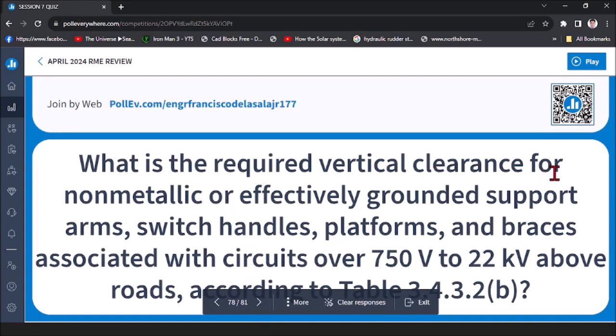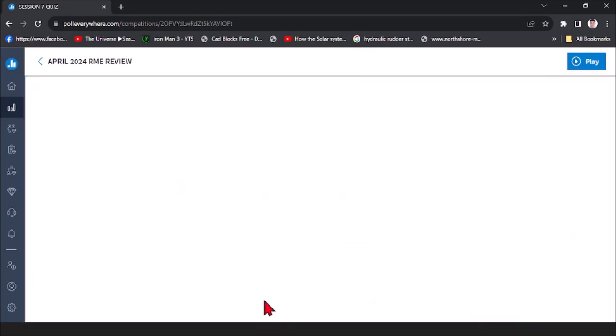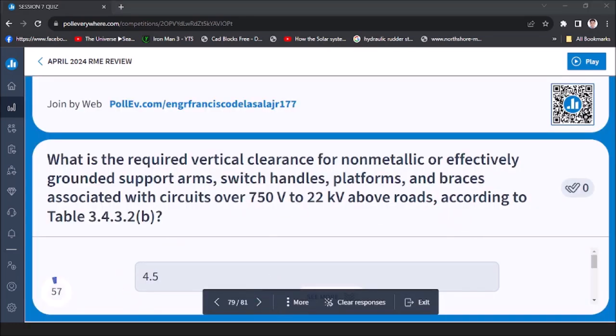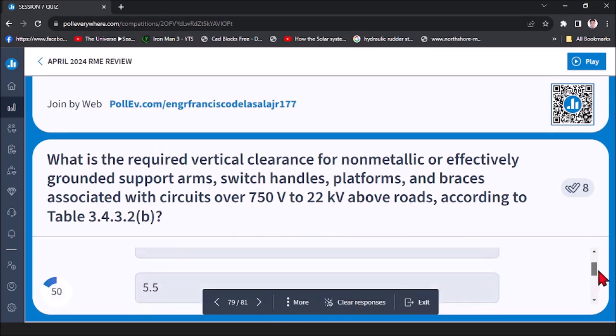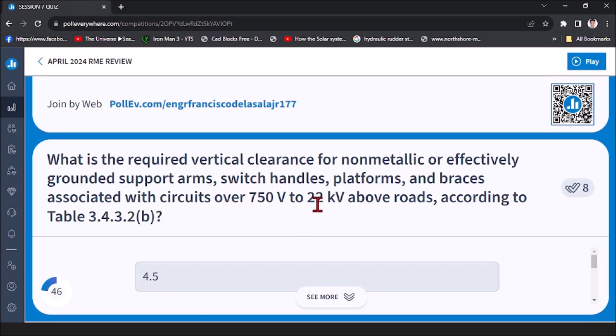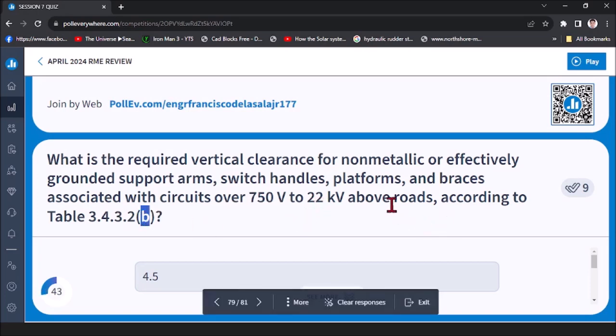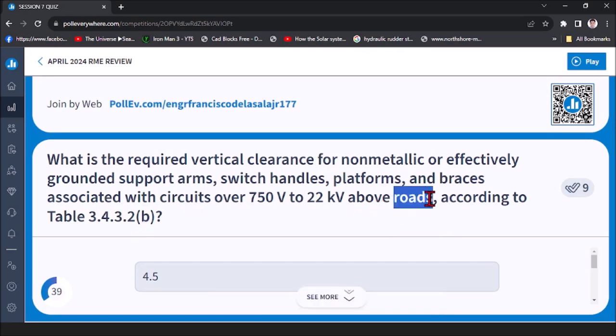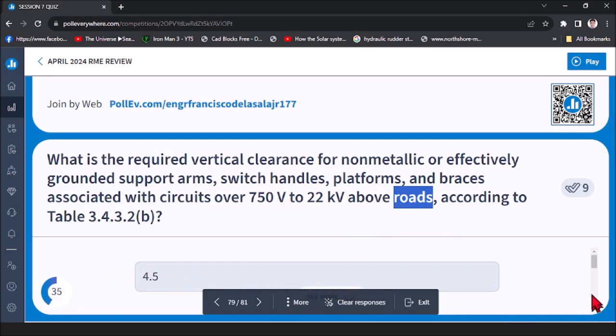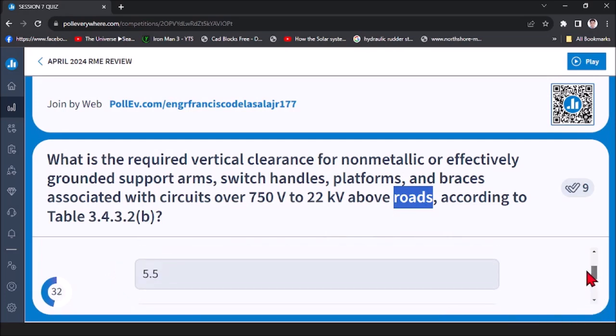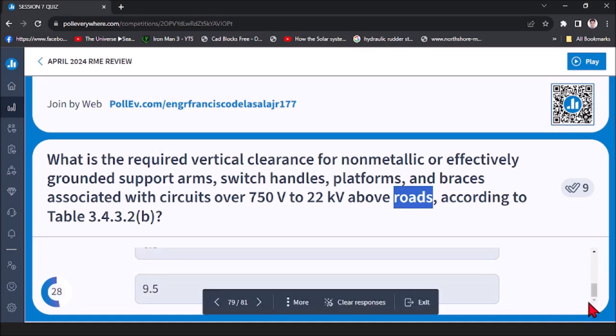What is the required vertical clearance for non-metallic or effectively grounded support arms, switch handles, and platforms and braces associated with circuits over 750 to 22 kV above roads according to table 3.4.3.2b? So I hope may screenshot kayo ng table, no? So hanapin niyo lang yung column for over 750 to 22 kV sa table B natin. Tapos yun yung kanyang column, tapos yung row na may roads. Alin yung ma-align doon na meters, so yun yung sagot sa question na to. So 30 seconds more.